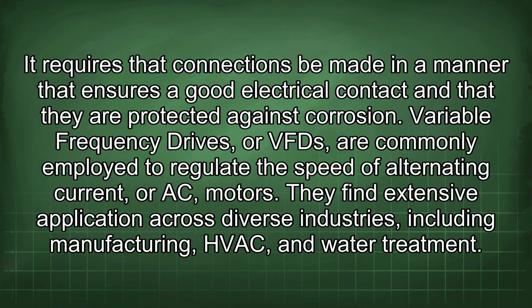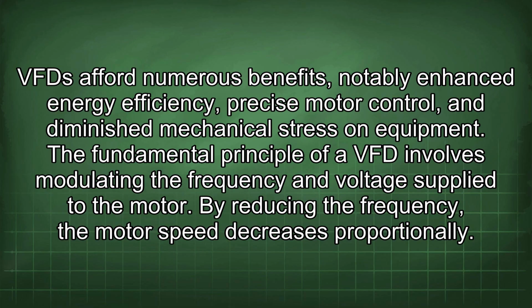Variable frequency drives, or VFDs, are commonly employed to regulate the speed of alternating current, or AC, motors. They find extensive application across diverse industries, including manufacturing, HVAC, and water treatment. VFDs afford numerous benefits, notably enhanced energy efficiency, precise motor control, and diminished mechanical stress on equipment. The fundamental principle of a VFD involves modulating the frequency and voltage supplied to the motor. By reducing the frequency, the motor speed decreases proportionally.